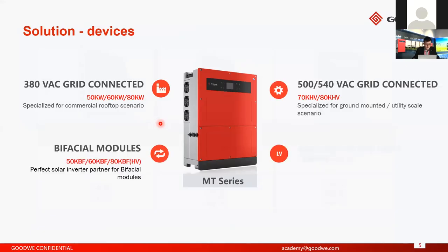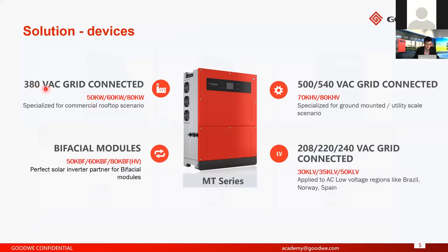And here are the details for the MT series. The standard product is 380 volts on the AC side. It's 50, 60, and 80 kilowatt. So it's very suitable for the commercial rooftop scenario. And also we have 500, 540 grid connect HV version products. So it's 70 kilowatt and 80 kilowatt. So it's very suitable for the ground mounted and utility scale scenario. And for the BF version, we have 50, 60, and 80 kilowatt. 80 kilowatt is HV version. It's a specific design only for the bifacial modules. And also, as I just introduced, we also have the LV version. It's 30, 35, and 50 kilowatt, but it's not used in India.